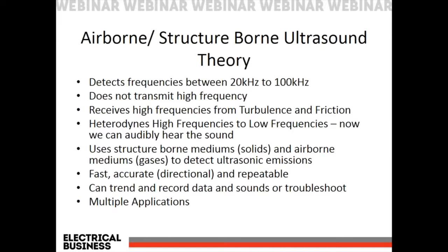So continuing on with some theory here, just a little 101 for everybody out there. Our ultrasound, as I mentioned before, detects frequencies between 20 kilohertz and 100 kilohertz. If we're familiar with our human range of hearing, it actually goes from 20 hertz up to 20,000 hertz, or 20 hertz up to 20 kilohertz. That's the human range of hearing, and that's obviously low frequency, or considered audible frequencies. Ultrasound starts at 20 kilohertz and goes above that, and that is considered high frequency sound. As I mentioned on the previous slide, our ultrasound does not transmit high frequencies whatsoever. We receive frequencies only, and how we receive them is basically in the line right below it.